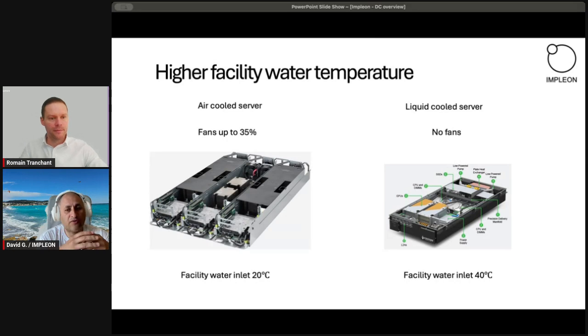Yes, of the server. But when we shift to the new CPU and GPU, the airflow needed is much more, because the temperature of the GPU is lower than the temperature of the CPU, and the heat flux is higher, so thermal resistance becomes more, and this is why we need much more flow rate, airflow rate, and this is why we have such a big number for the fans energy consumption.